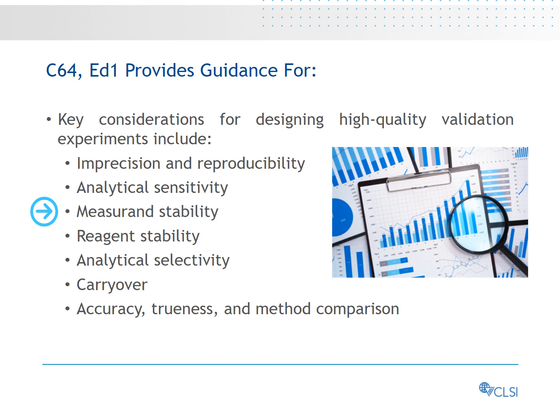Measurand stability is validated to ensure that the error in measuring concentration, which is a function of defined specimen handling conditions, does not exceed the acceptance criteria. Reagent stability is validated to demonstrate that the storage conditions and duration for reagents are adequate to meet the test's analytical performance criteria. Evaluation of analytical selectivity is a key component of method validation. Endogenous and exogenous compounds, as well as compounds generated during specimen processing, can cause interference in quantifying or qualifying ions for the measurand and/or internal standards. The test developer should evaluate carryover potential by analyzing samples in the intended matrix with low, median, and high-measurand concentrations.